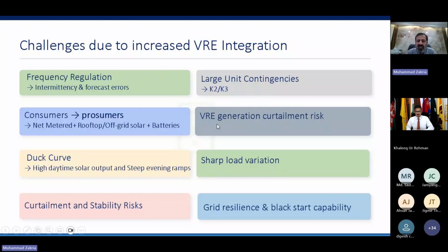VRE generation curtailment risk - yes, as VRE increased, curtailment happens due to two factors. One is demand decline. At present our demand has declined such that during 11 to 12 hours we are at the maximum low level of demand for September in our history. So what we are doing is controlling frequency by curtailment of generation resources, including VREs, even though these are must-run buses, but we have no choice to meet this demand deficit issue.